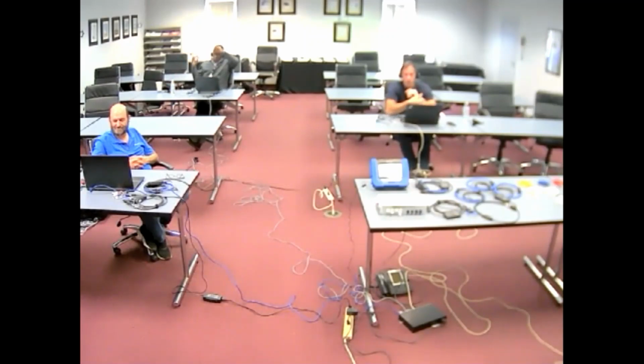But just to briefly answer your question, you have the ability in DranView, and certainly in the instrument itself, though it's easier in DranView, to view any voltage channel, any current channel, the voltage or the current, or individual harmonics that may have been recorded by the instrument, or the VTHD and ITHD. But we'll definitely elaborate on that in our next session when we cover the IEEE 519 harmonics, because it directly relates.